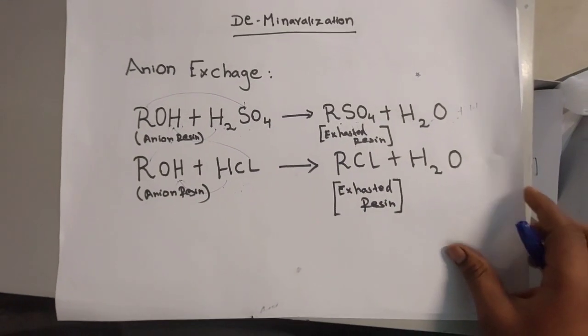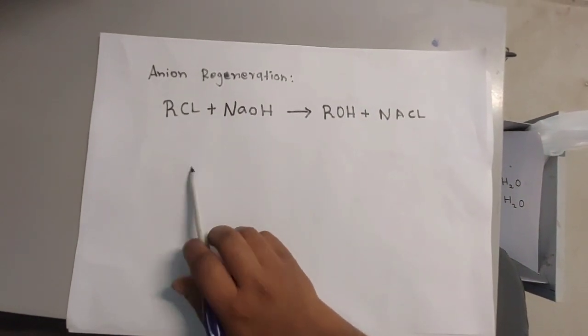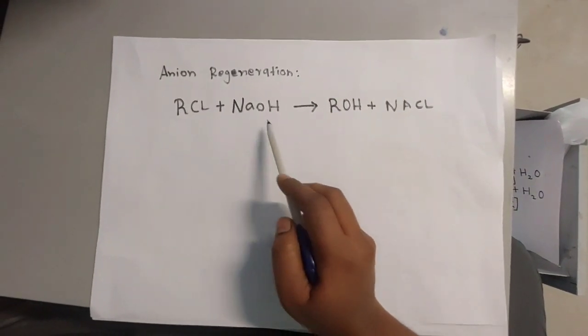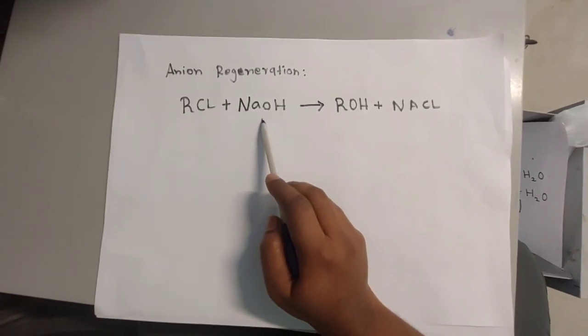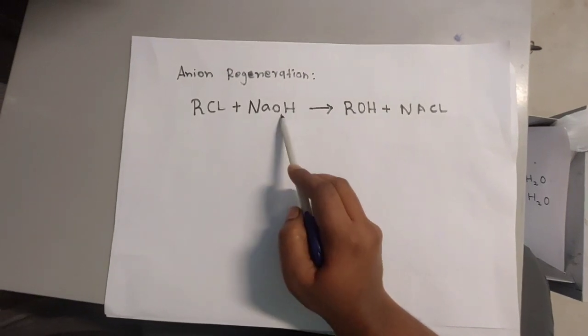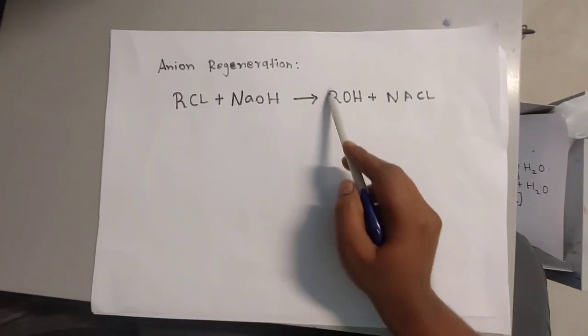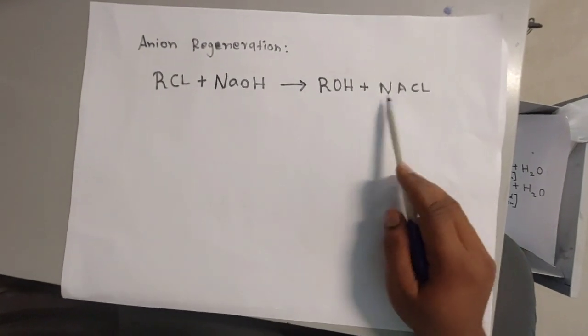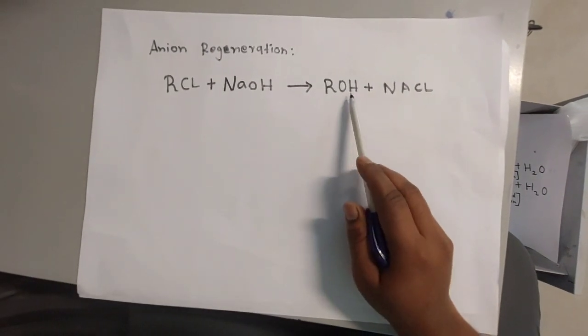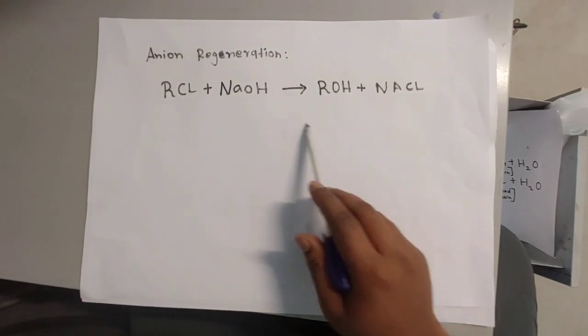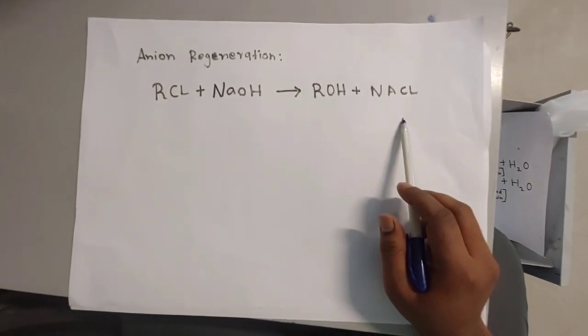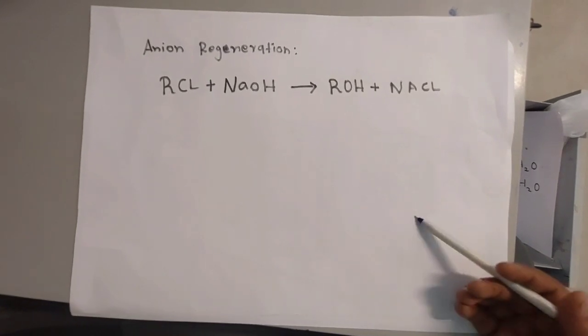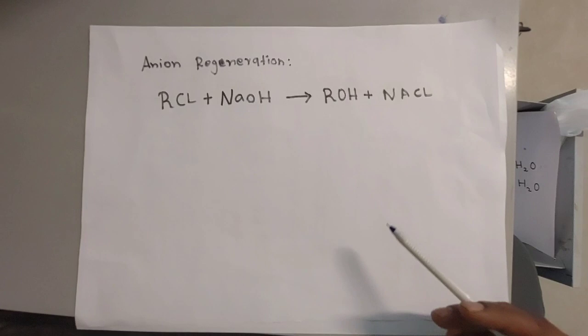I will show you the chart. For example, chloride, sulfate — everything comes in and separates. The resin holds the chloride. We are using sodium hydroxide — caustic soda — for regeneration. The reaction: the OH goes into the resin, making it ROH — that is the pure resin — and sodium chloride goes to drain as waste. Finally we get the pure resin. This type of regeneration method we continue for many days. Now I will operate the regeneration for my de-ionization plant and show you in this video.